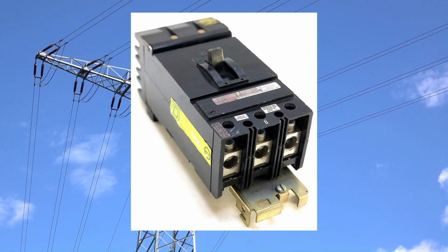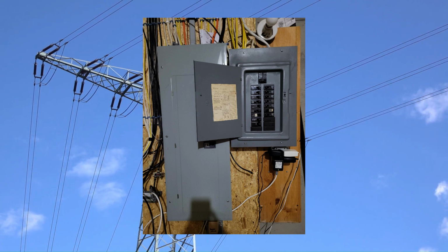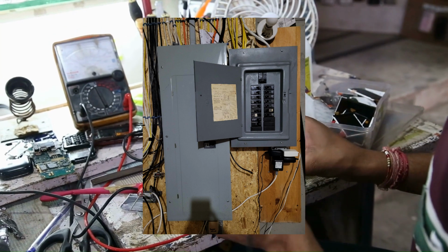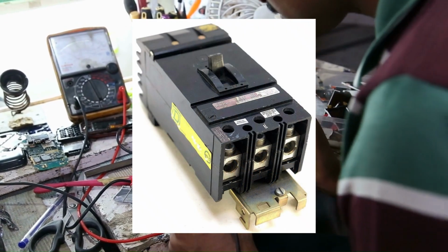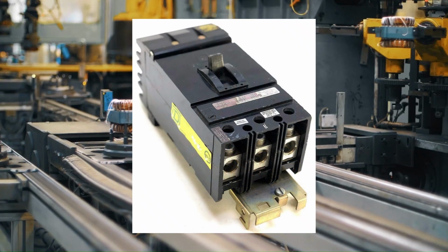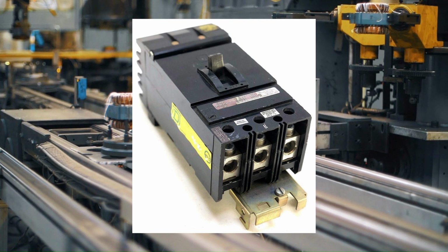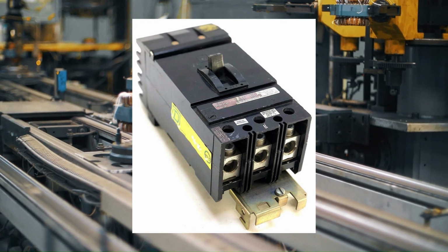The maximum current that a fuse or circuit breaker can safely interrupt is known as the interrupting current rating, also known as short circuit rating. A protective device may actually rupture, resulting in further harm, if a fault current surpasses a level that it cannot interrupt. The rating for interrupting current is much higher than that for continuous current and should be far higher than the highest current that the power source is capable of supplying. 10,000 A, 50,000 A, and 100,000 A are typical interrupt ratings.